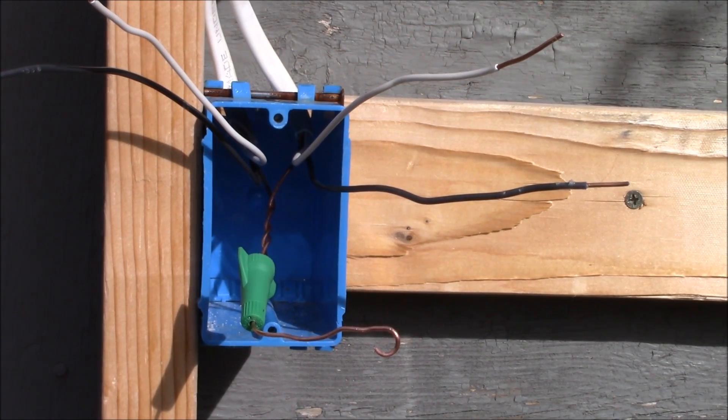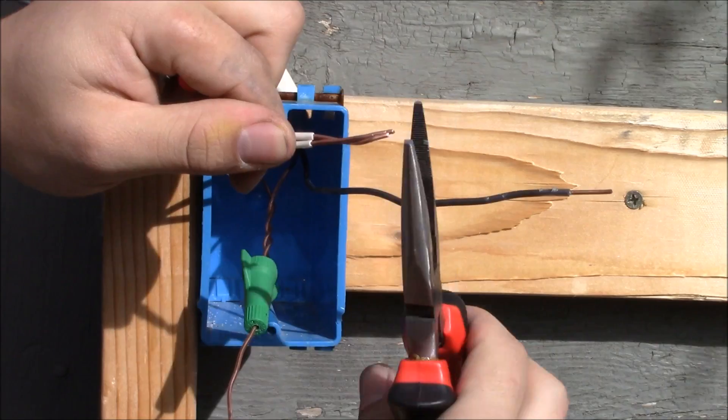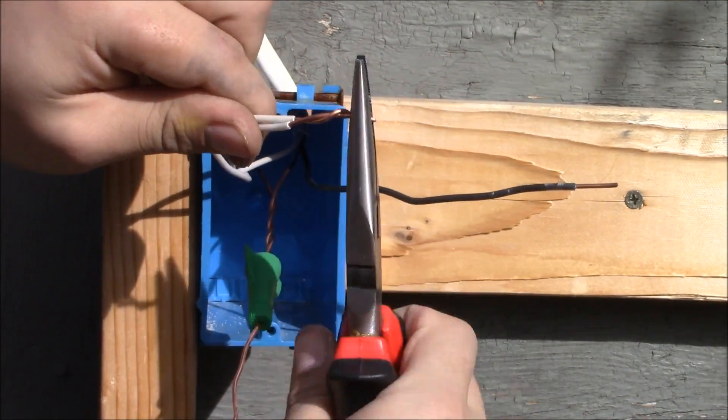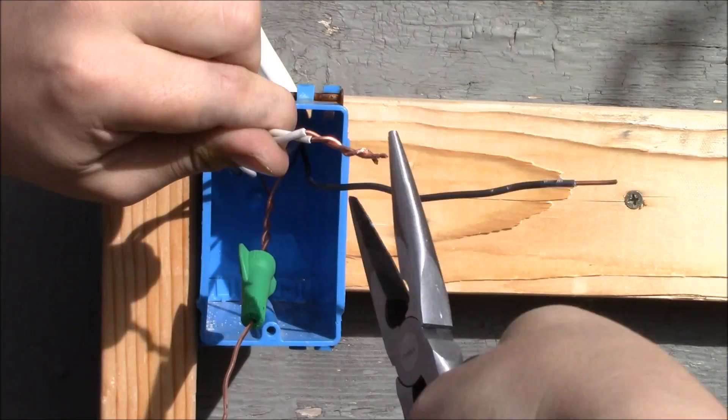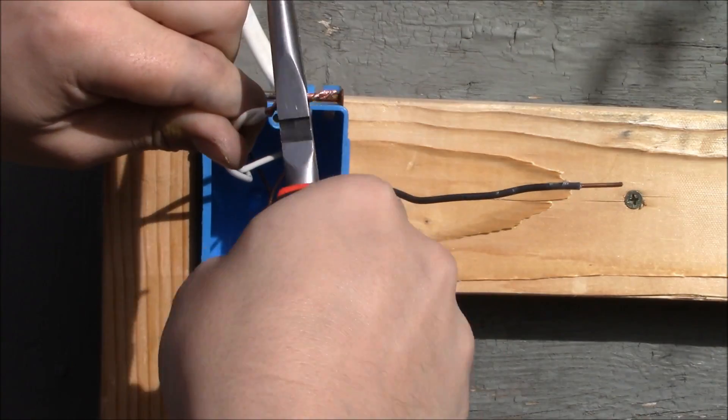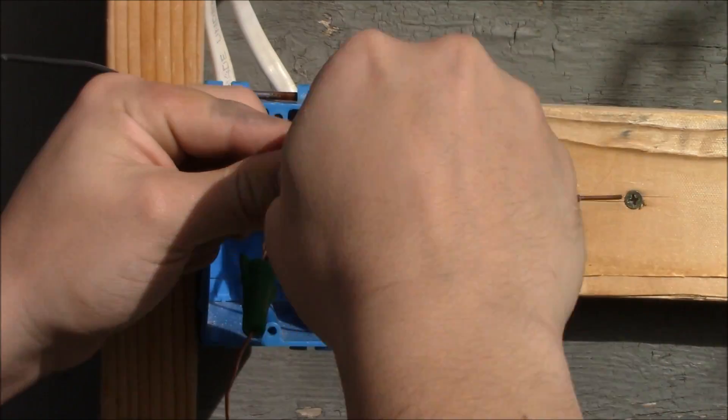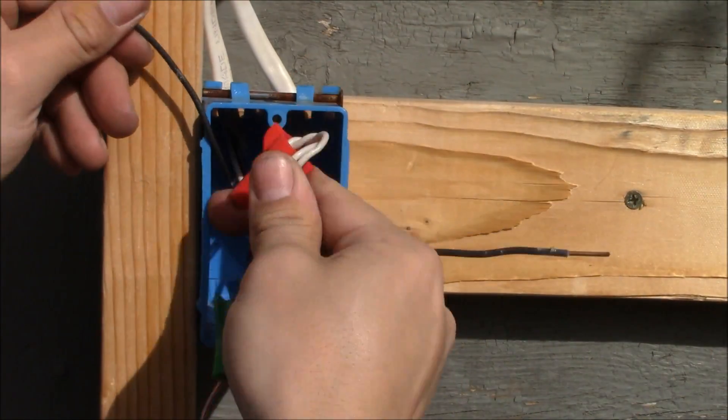Now we're going to connect together the neutrals. The neutrals are not used in single pole switches, but it has been code since 2011 that all switch boxes need to be provided with neutral wires. Now we're going to splice them together and use a wire nut, then place them in the back of the box.